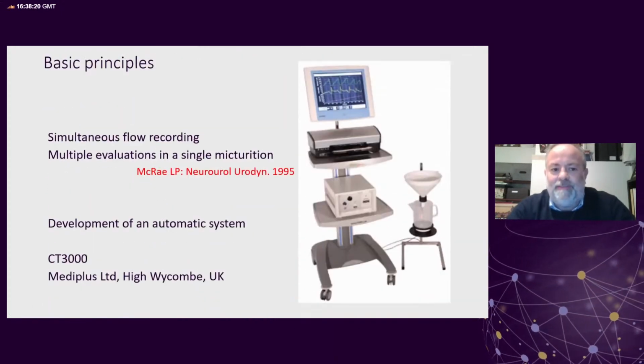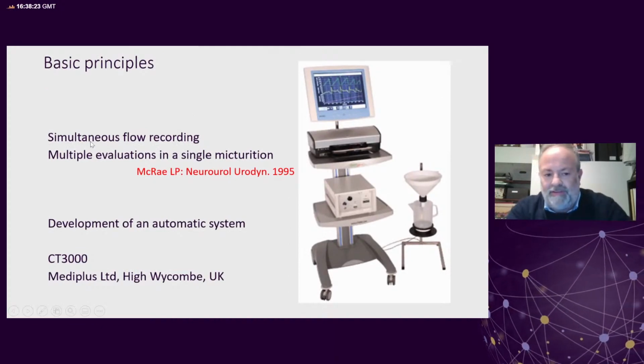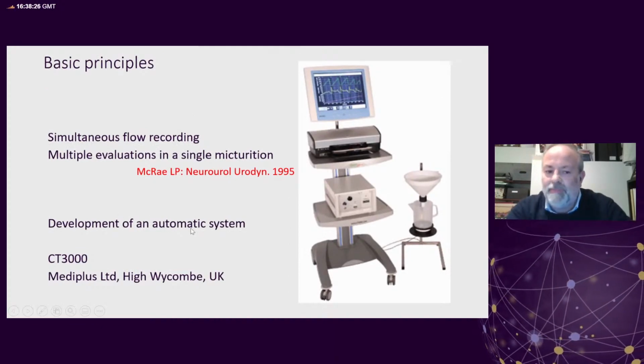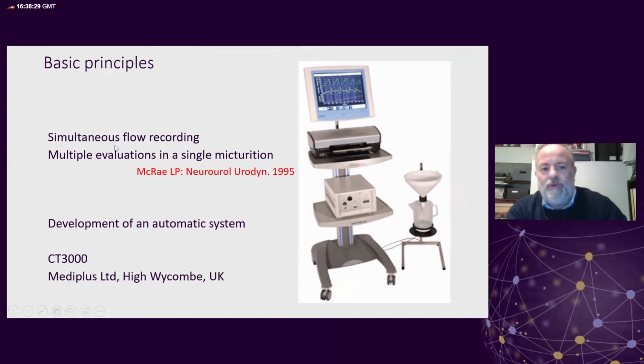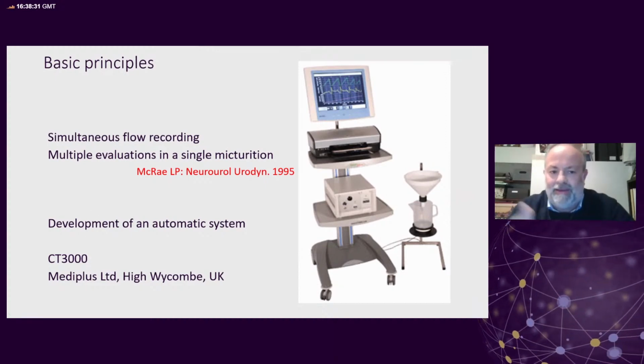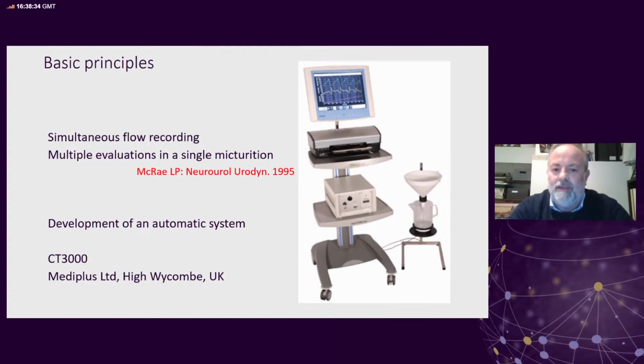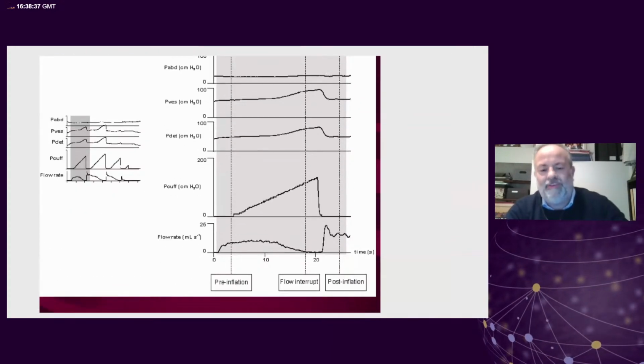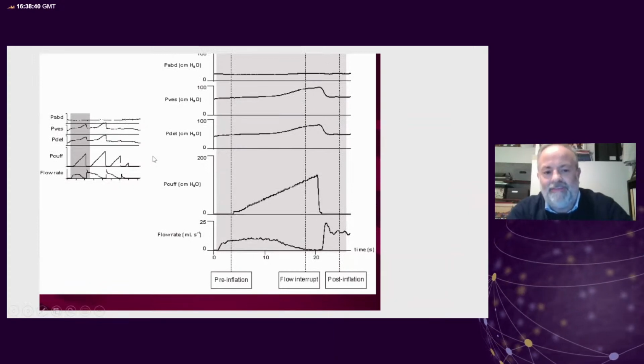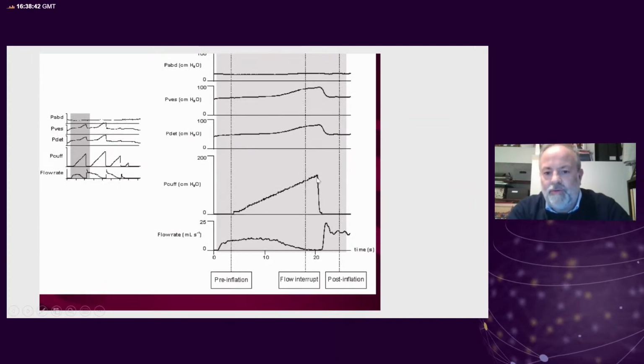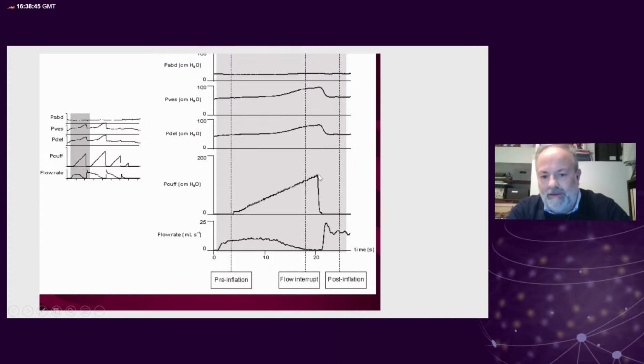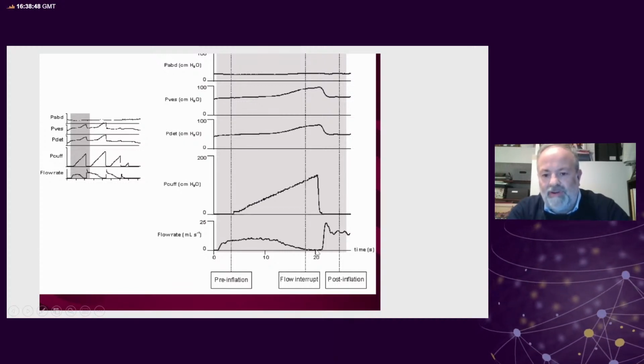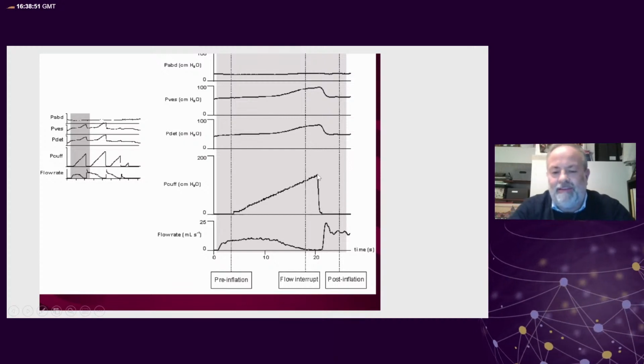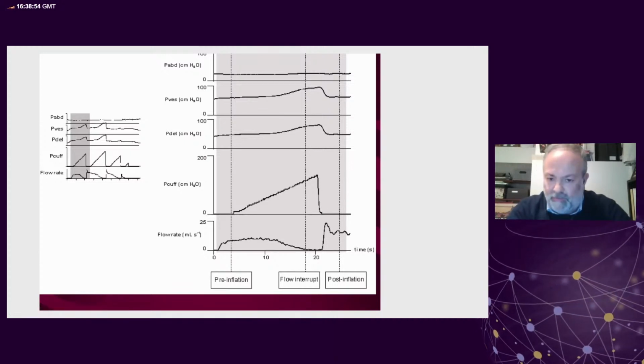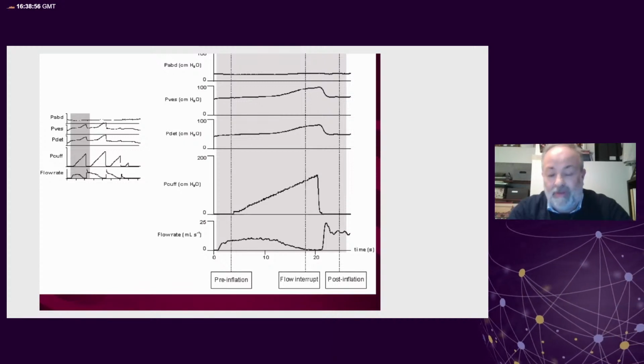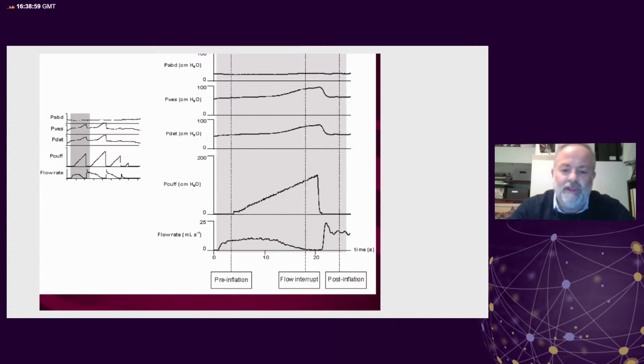So on these basic principles, there was also a development of an automatic system called CT3000, allowing simultaneous flow recording and also multiple evaluations during a single micturition. Here we see the typical traces coming from this test. Here you see the increase of the penile cuff pressure. Here is the moment where the flow stops, and this is the isovolumetric detrusor bladder pressure recorded for this patient.